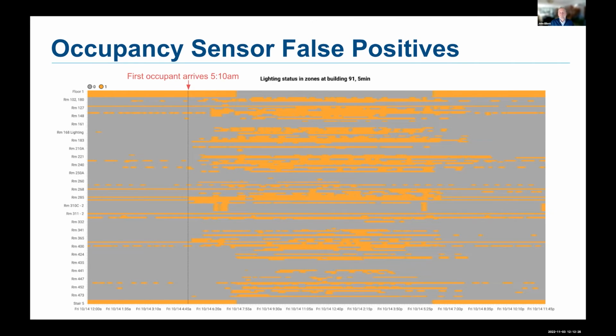But in particular, what we see is that in lab spaces, we see many false positives. Those are associated with heat sources and motion in laboratories, triggering false positives in occupancy sensors that are either misspecified or misinstalled. So you can just get a feel for the issue here. This is in one building across many different zones. These are the 24 hours in a day. And you can see, we know no one is coming into this building before 5 a.m., but you can see all these blips of occupancy happening all through the night. And those in general are laboratory spaces, and those are heat sources or motion that's happening in the laboratory.